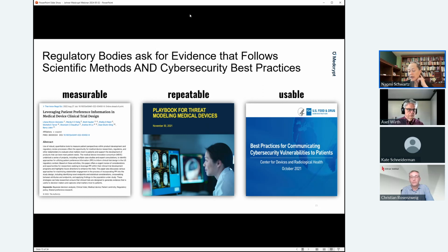Now, Axel mentioned that in some cases there are care delays because of cybersecurity measures implemented to deal with ransomware, for example, more complex passwords. And that is a real issue. FDA is very cautious about usability impact related to cybersecurity controls. So when you have a situation where you are concerned about the potential for a usability impact, you do need to raise your hand and ask your regulatory body how to find a good balance for usability and cybersecurity. That is absolutely critical. Next slide.